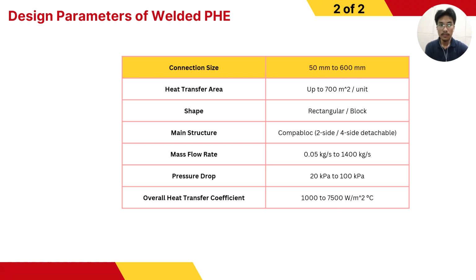So for pressure drop, it depends on the size of the overall welded PHE. So for the allowable pressure drop to increase, the size of the overall plate heat exchanger must be decreased. And in another way, if the allowable pressure drop is to be decreased, the size of the overall PHE should be increased. So it is inversely proportional to the size of the welded PHE. So last, the overall heat transfer coefficient ranges from 1,000 to 7,500 watts per square meter degree Celsius. This parameter is typically denoted as small letter k or capital letter U.